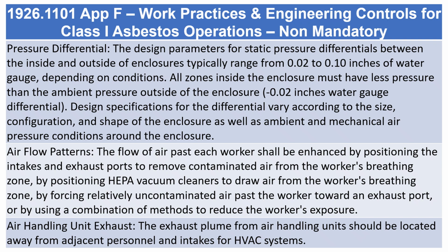All zones inside the enclosure must have less pressure than the ambient pressure outside of the enclosure, minus 0.02 inches water gauge differential. Design specifications for the differential vary according to the size, configuration, and shape of the enclosure as well as ambient and mechanical air pressure conditions around the enclosure.